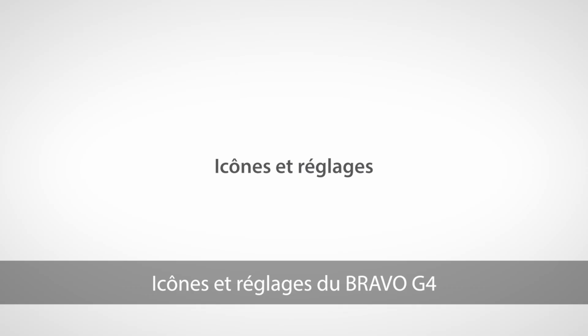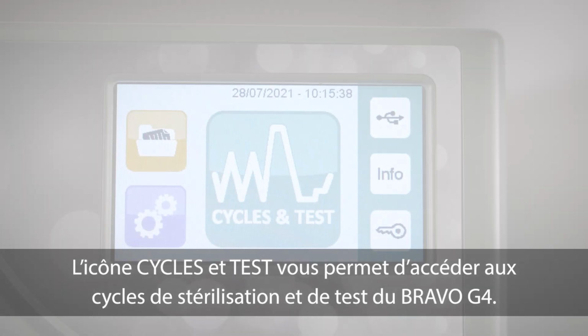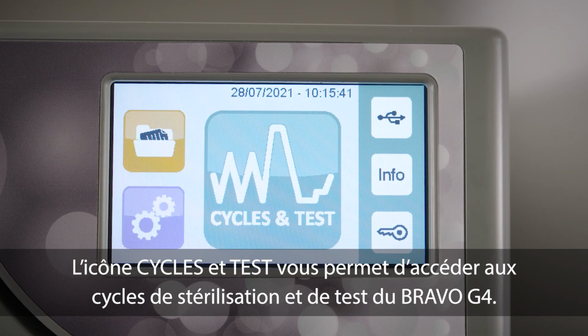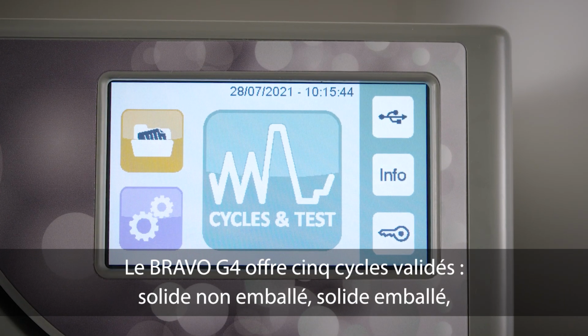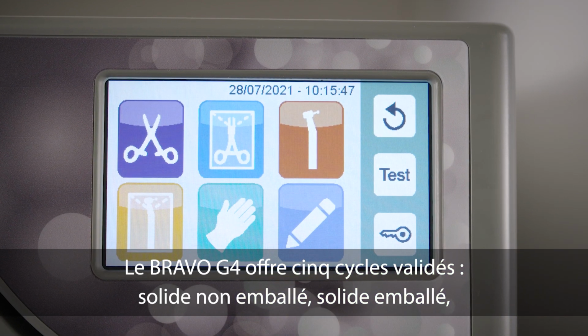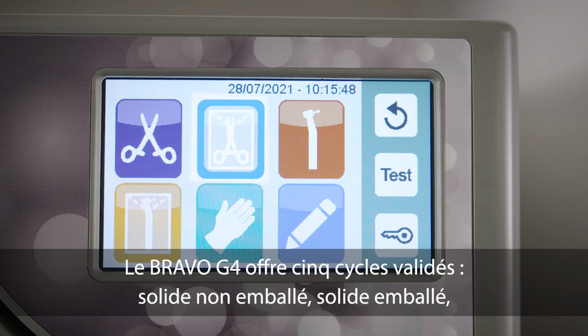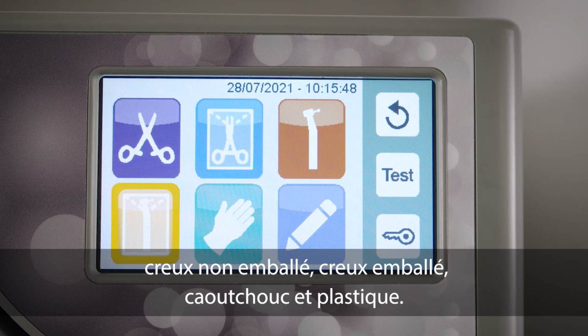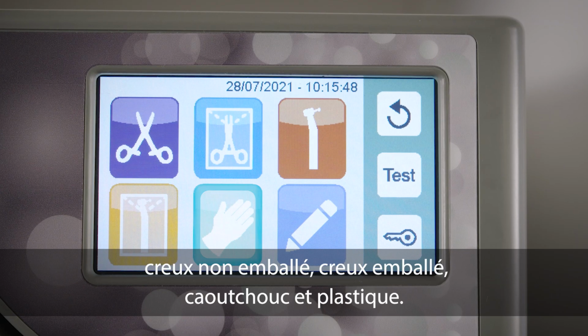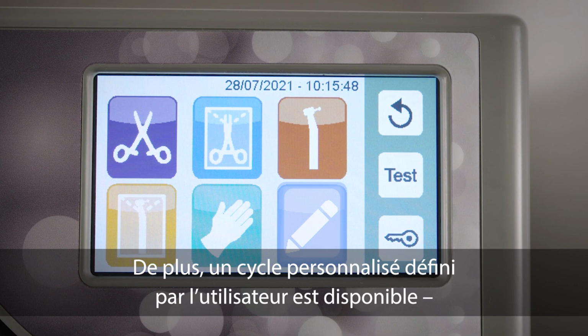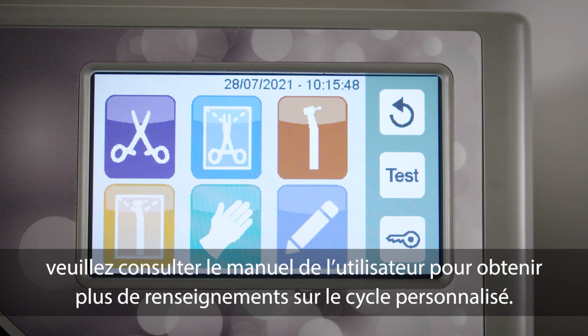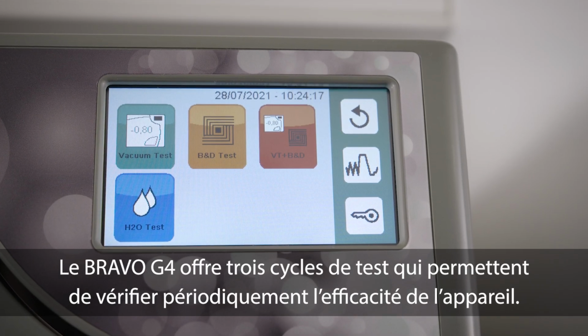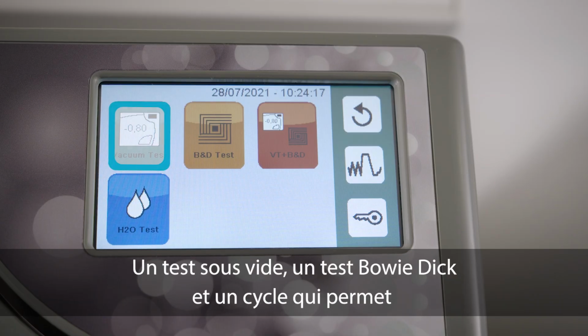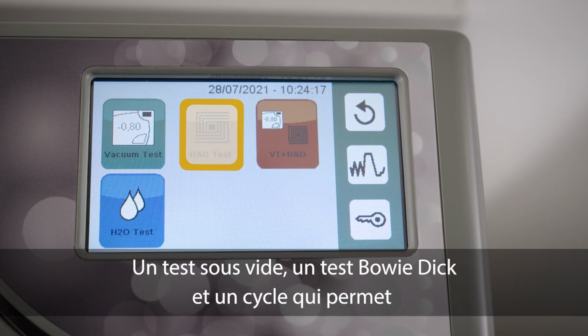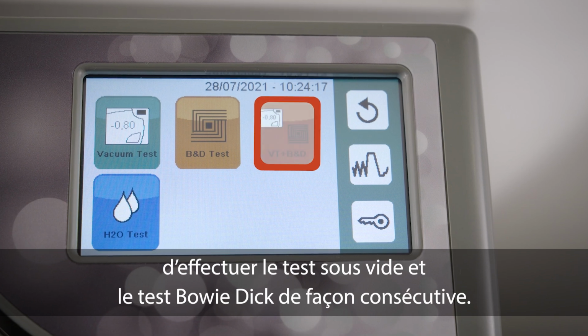Bravo G4 icons and settings. The cycles and test icons give you access to the Bravo G4's sterilization and test cycles. The Bravo G4 offers 5 validated cycles, including solid unwrapped, solid wrapped, hollow unwrapped, hollow wrapped, and rubber and plastic cycle. In addition, a user-defined custom cycle is available. Please consult the operator's manual for more information about the custom cycle. The Bravo G4 offers 3 test cycles to periodically check the unit's effectiveness: a vacuum test, a Bowie-Dick test, and a cycle that allows the vacuum and Bowie-Dick test to be run back-to-back.